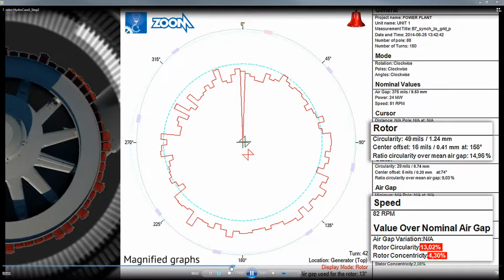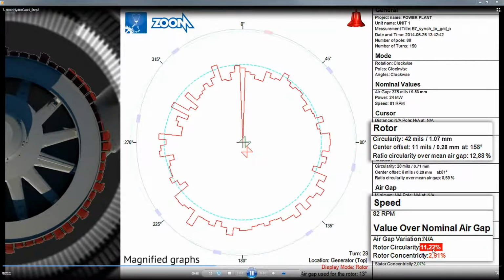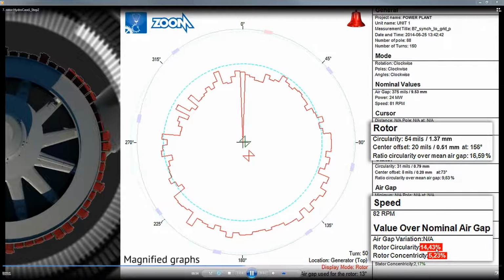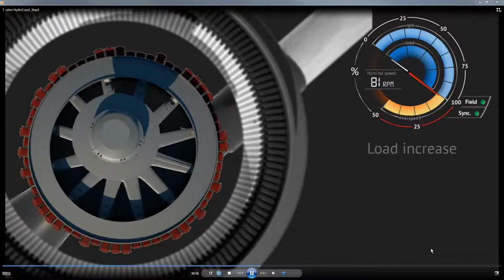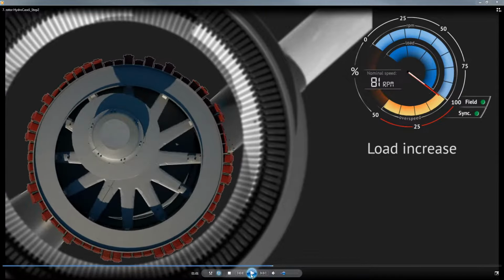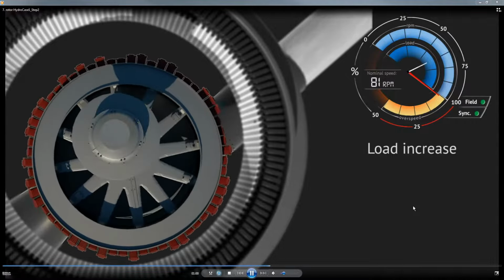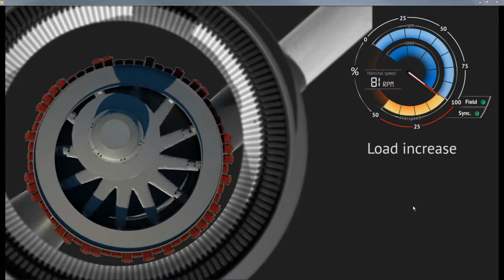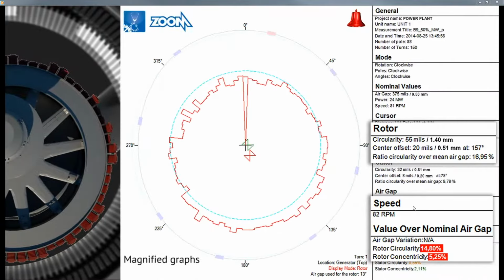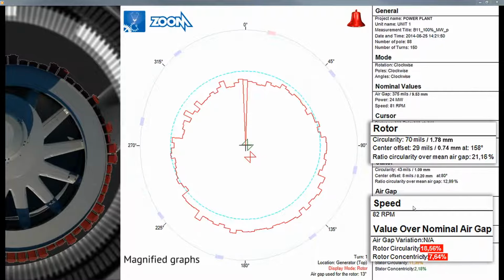So if I go back to the original rotor, sorry, I'm trying to capture the numbers: 10.15, 11.22, circularity 11.96. This is during the same measurement, 13.02, 14.43, during the same measurement. So introducing the field coming from the core caused serious distortions to the rotor, and in fact pulled it towards downstream a bit. And as you can see, as they increased the load, the unit slowly pulled towards downstream. So that same rotor, as they increased the load, was slowly being pulled downstream.